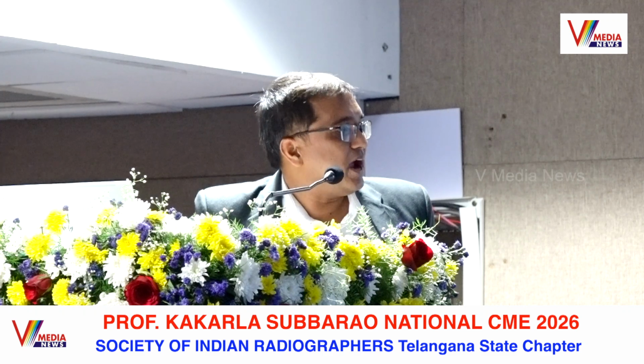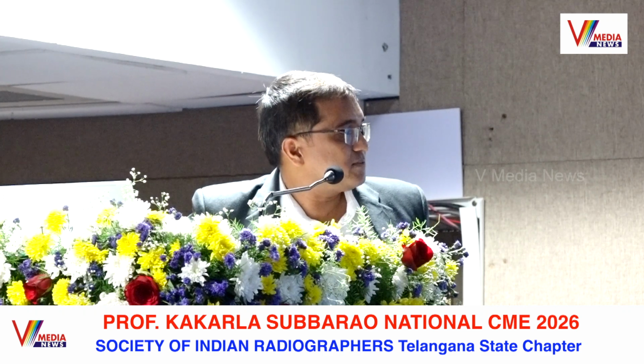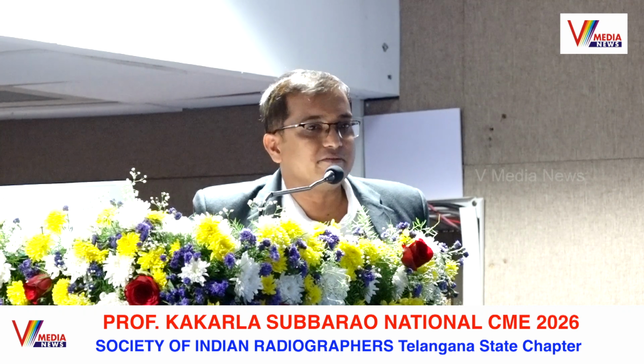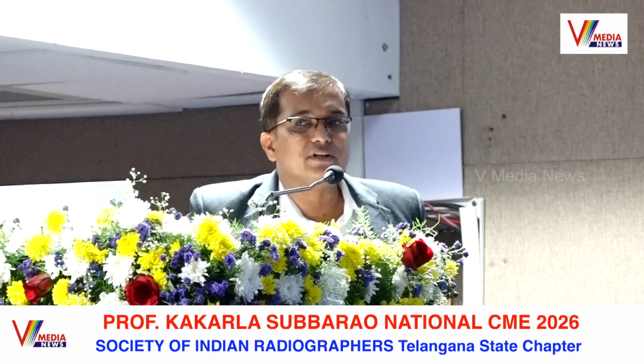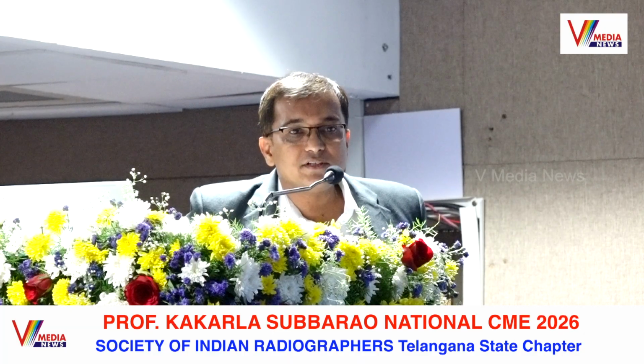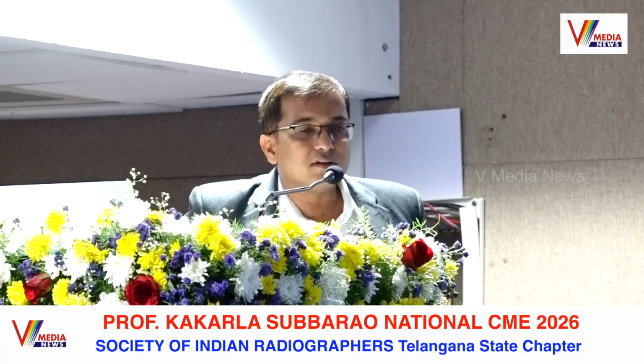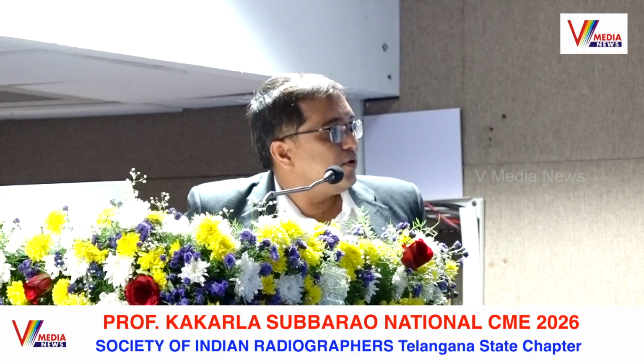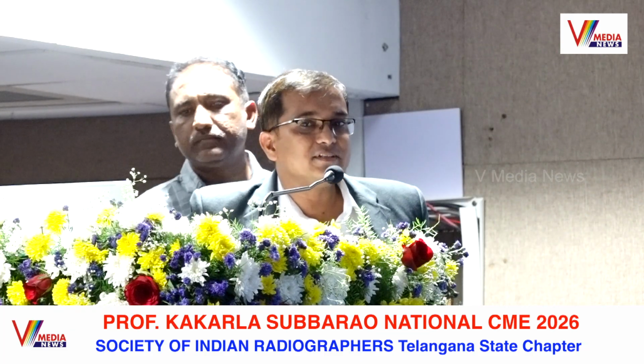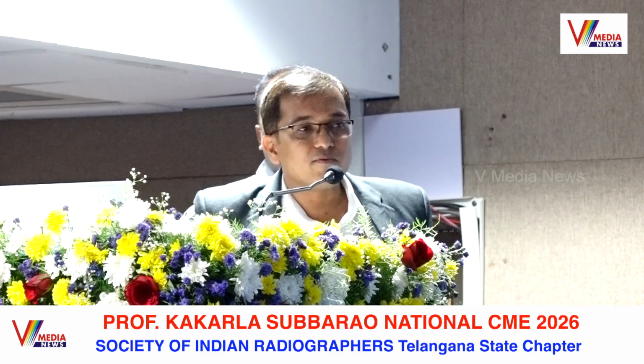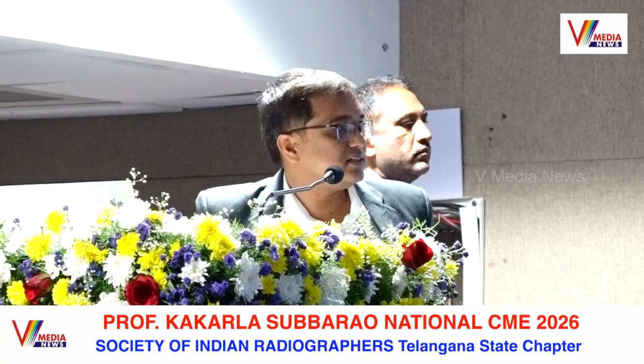And the lead apron should be handled like this, and the QA test must be done every 2 years for the equipment, even for the C-arm, whether it is operating in ERCP or the operation theater. If you are doing everything, then you can confidently face the NABH team if you are following the radiation safety practices.